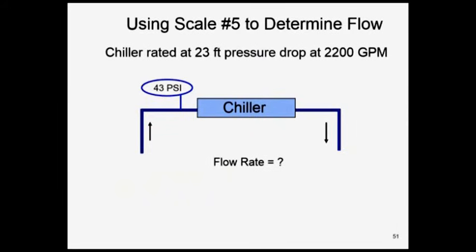Now, we already know from submittal, you got submittal laying in front of you, that a clean chiller would have 2,200 GPM at 23 feet of drop or 10 pounds drop. You already know that. So my question to you is, what is the pressure drop across that chiller now? First of all, we're going to take a pressure reading with a gauge going into the chiller and a pressure reading with the gauge coming out of the chiller. In this case, the pressure going in is 43. The pressure coming out is 32 pounds. So the pressure drop is 11 pounds.